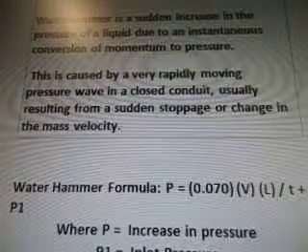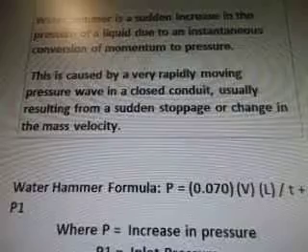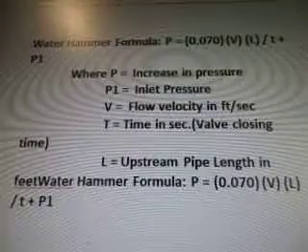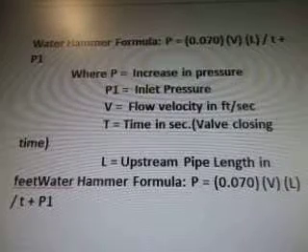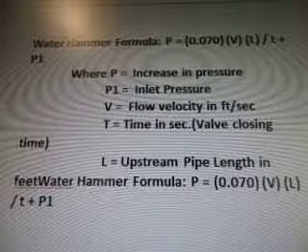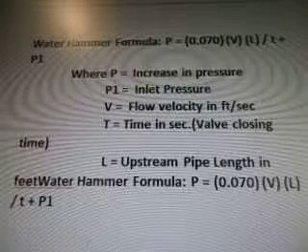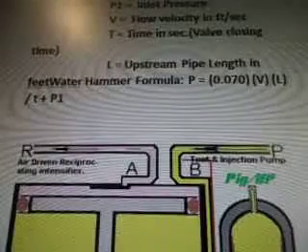Water hammer is a sudden increase in the pressure of a liquid due to an instantaneous conversion of momentum to pressure. This is caused by a very rapidly moving pressure wave in a closed conduit, usually resulting from a sudden stoppage or change in the mass of velocity. Water hammer formula: P equals 0.070 × (V × L) / T + P1, where P is increase in pressure, P1 is inlet pressure, V is flow velocity in FT/S, T equals valve closing time in seconds, and L is upstream pipe length in feet.